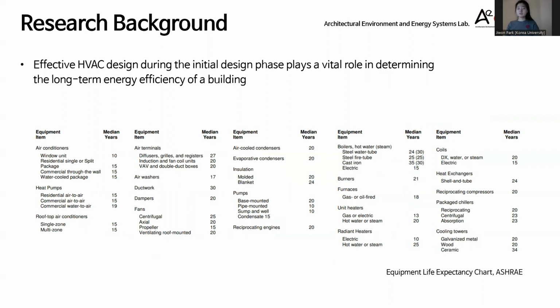The table below is the equipment life expectancy chart provided by the American Society of Heating, Refrigerating, and Air Conditioning Engineers. According to the chart, the life expectancy of a chiller is around 20 years. Based on this table, the performance of the chiller determined during the design phase will determine the cooling energy efficiency of the building for 20 years.